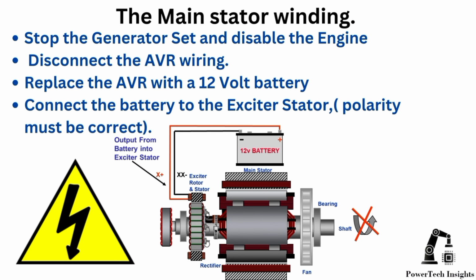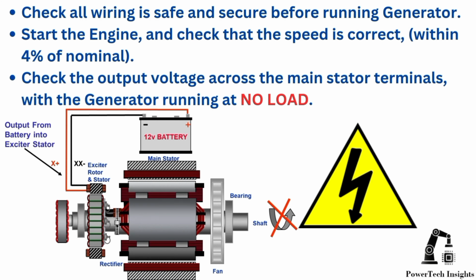Part 1. The main stator winding. In this part, we will provide a comprehensive guide on fault diagnosis for the main stator winding. Let's get started. Stop the generator set and switch off the engine control circuit. Follow lockout-tagout, LOTO procedure. Disconnect the AVR wiring. Replace the AVR with a 12-volt battery. Connect the battery to the exciter stator. Polarity must be correct. Check all wiring is safe and secure before running the generator.